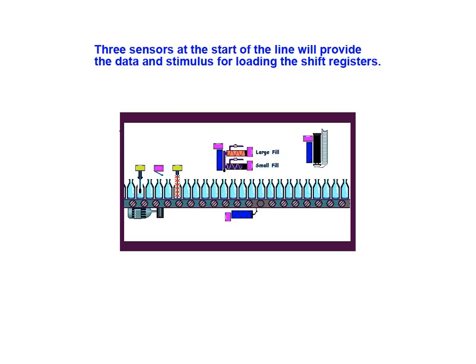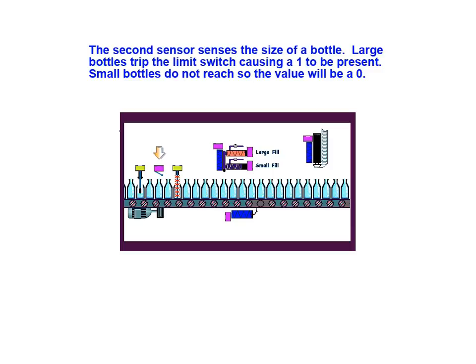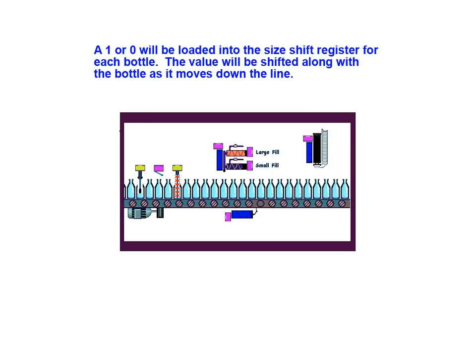Three sensors located at the start of the line will provide the data and stimulus for loading the shift registers. The first sensor senses the arrival of a bottle on the line and can be used to trigger a shift in the registers. The second sensor senses the size of the bottle underneath it. Large bottles trip the limit switch causing a 1 to be present, while small bottles do not reach the limit switch so the value remains at 0. A 1 or 0 will be loaded into the size shift register for each bottle and shifted along with the bottle as it moves down the line.